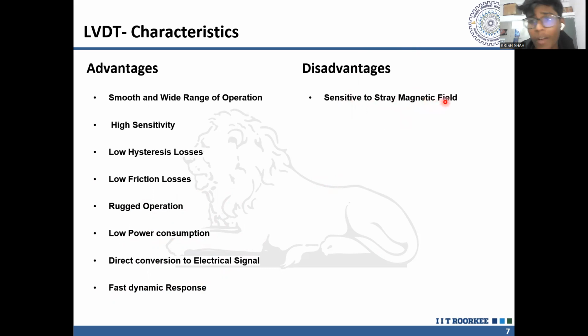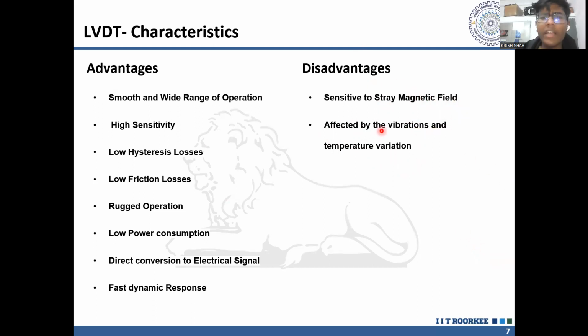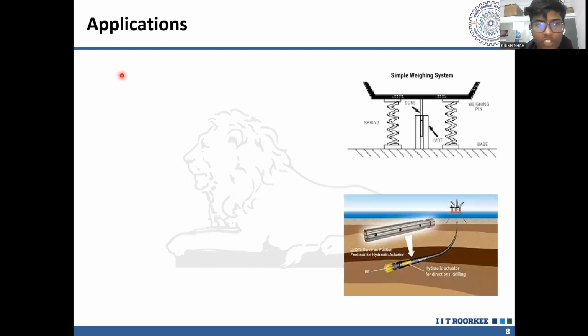Disadvantages: it is sensitive to stray magnetic fields. As the principle depends on electromagnetic induction, a stray magnetic field can affect the result of the LVDT output, and it is also affected by vibration and temperature. Vibration may lead to displacement of the core, and thus it can give bad results. The linearity range is very small for a particular size. So for a particular size of LVDT, we have a particular range from some centimeters to some centimeters, which is a disadvantage in some cases. Therefore, people try to increase the linear range of the LVDT.